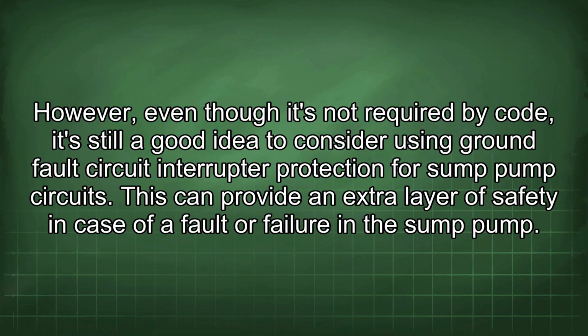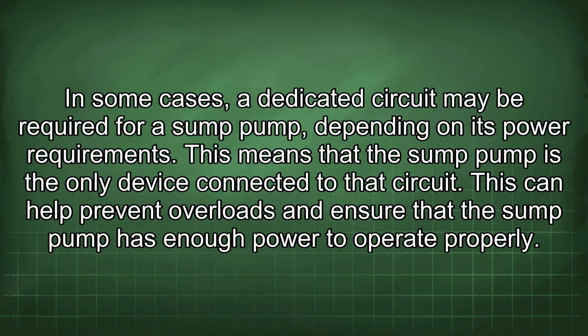This can provide an extra layer of safety in case of a fault or failure in the sump pump. In some cases, a dedicated circuit may be required for a sump pump, depending on its power requirements. This means that the sump pump is the only device connected to that circuit. This can help prevent overloads and ensure that the sump pump has enough power to operate properly.